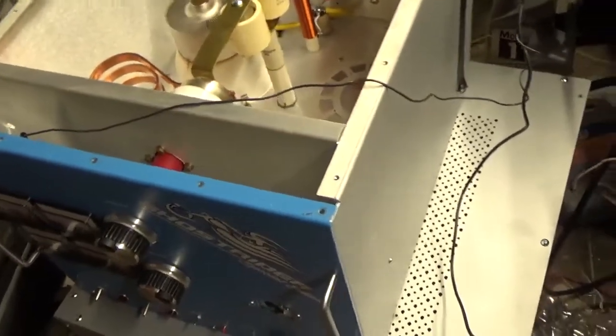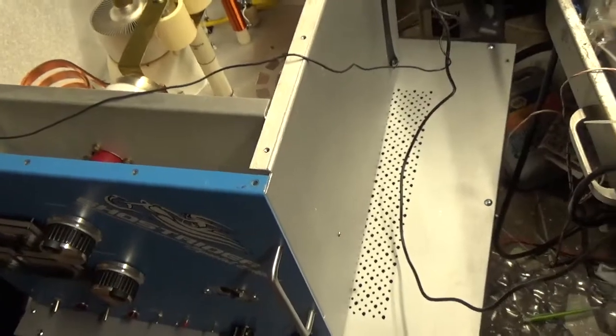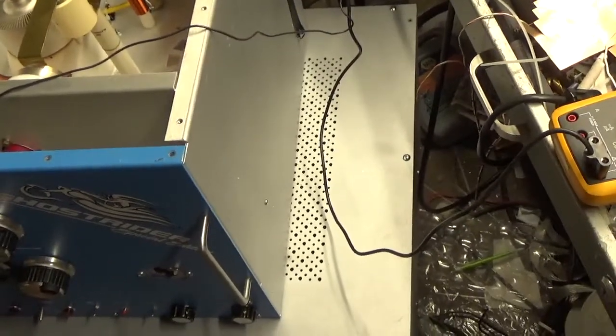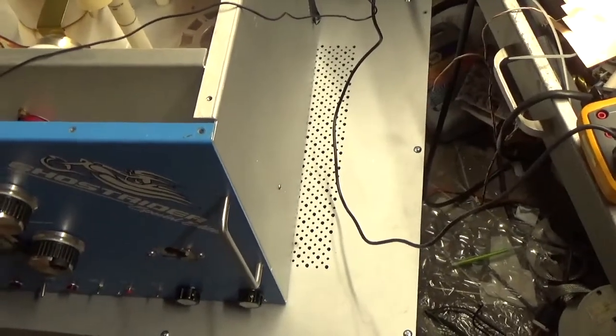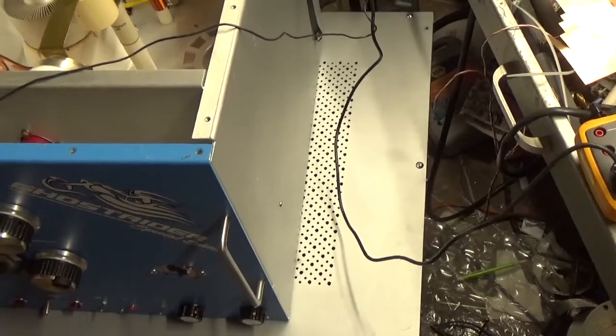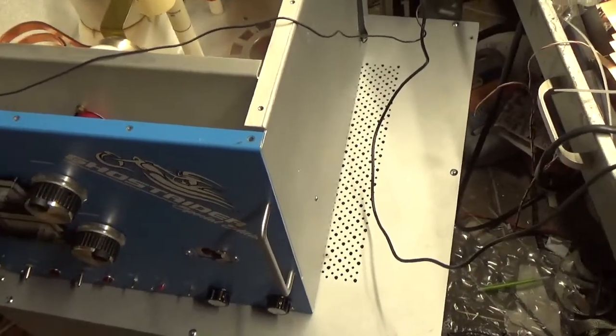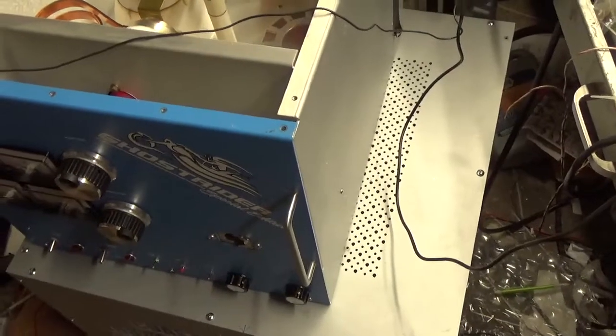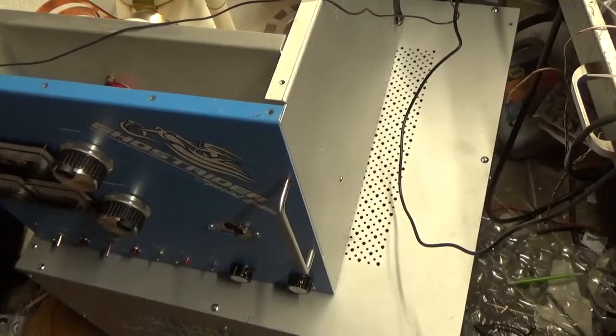We had to fix a couple things yesterday, one of which was the power supply had a 4 ohm resistor in there for the soft start, and every once in a while it would trip the breaker. So we put a 20 ohm in, now we're good to go. I had to replace the relay under here too.